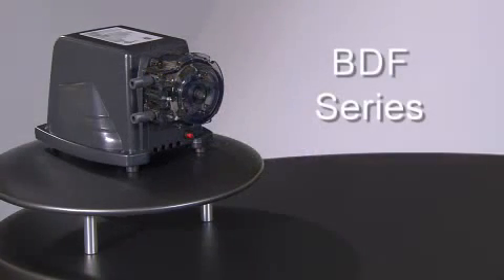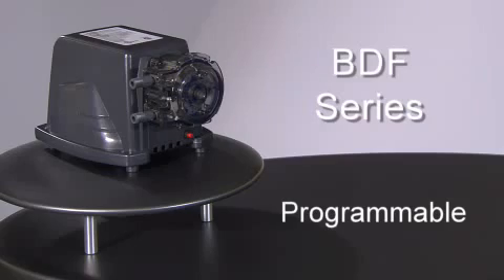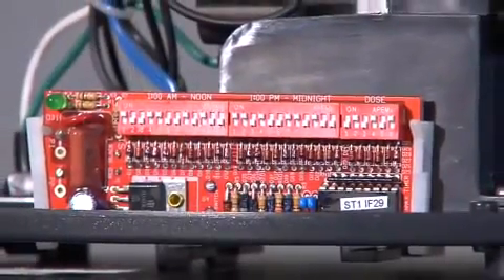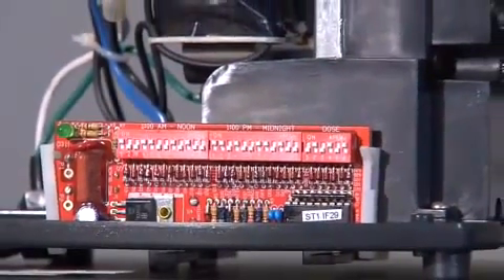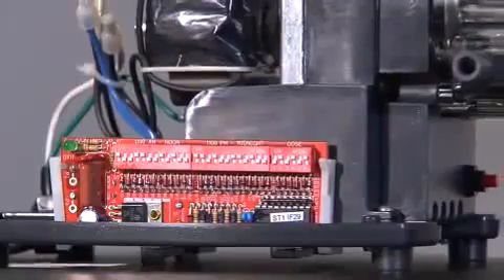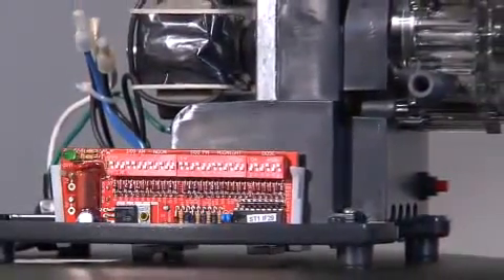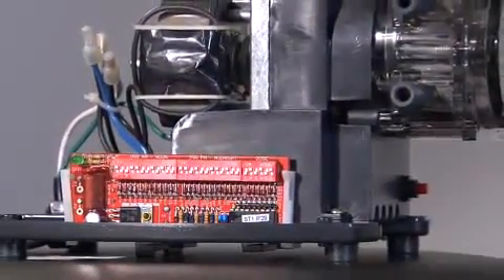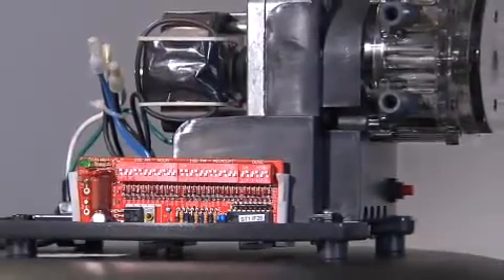The BDF Series is equipped with a low RPM motor and utilizes the same pump head as in the Classic and SVP Series. The pump can be programmed to provide the most efficient and effective dosing schedule and dosage amounts for treatment. Inside the motor housing, a programmable timer is activated by dip switches to provide a 24-hour or 7-day dosing schedule, up to 24 events a day and 21 ounces per event.